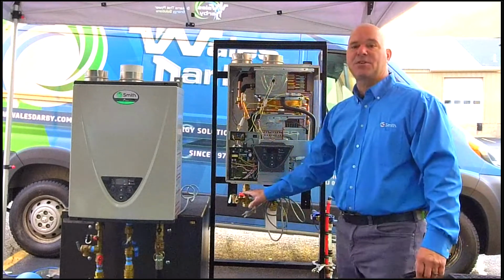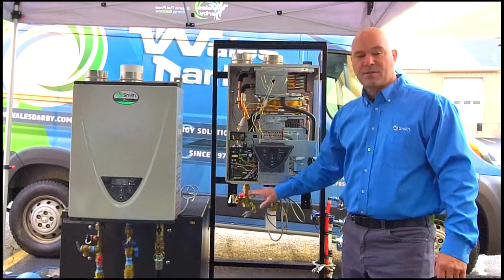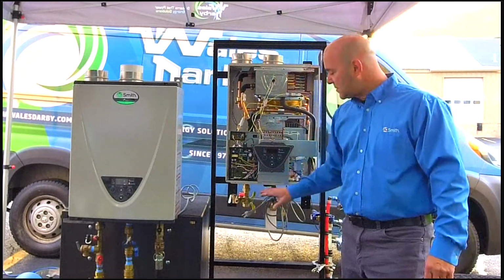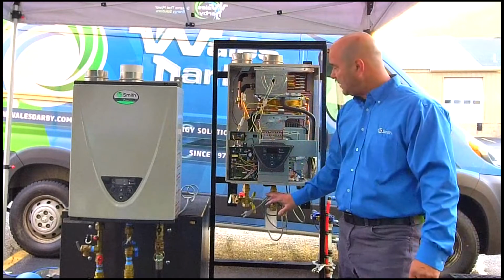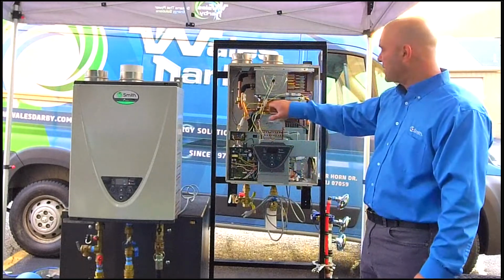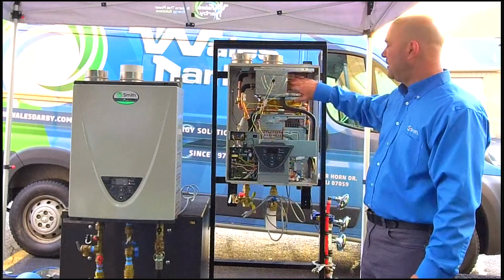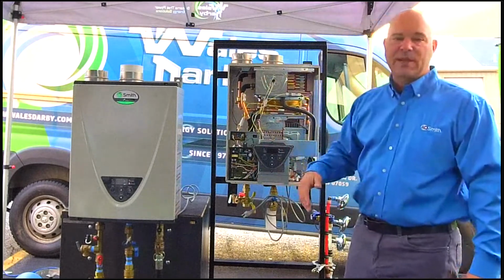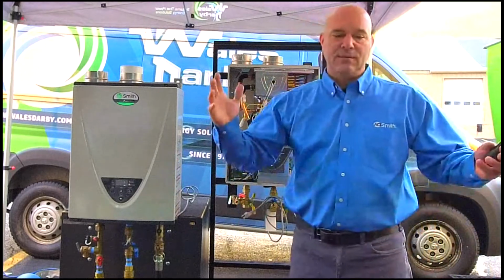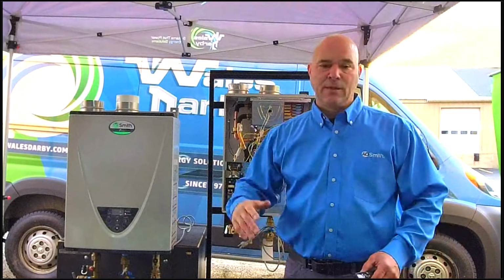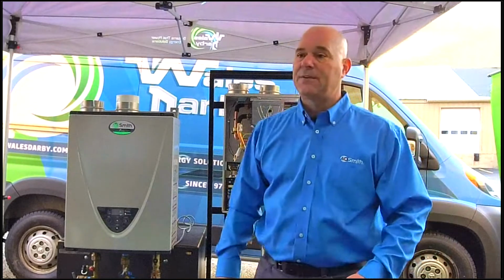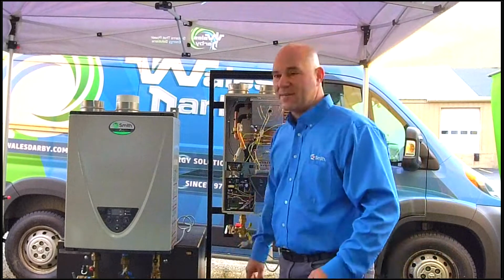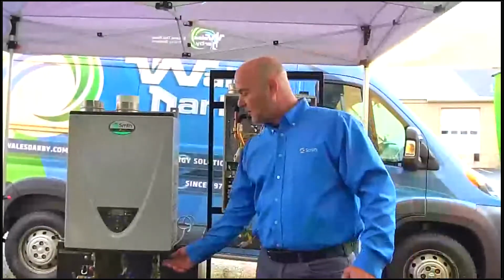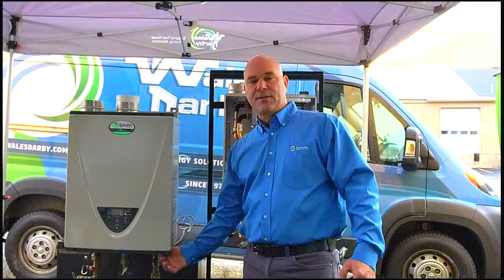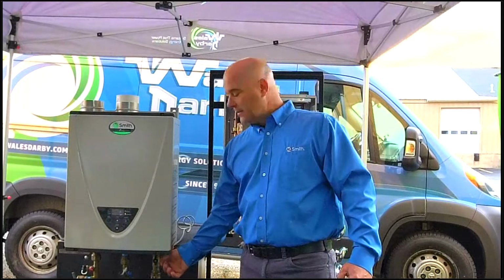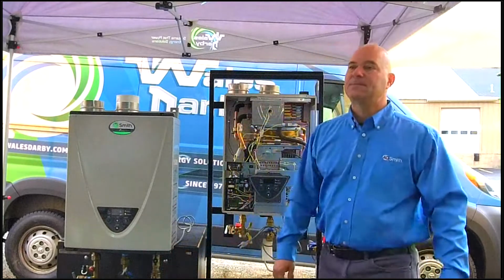The reason for that is we want to make sure that we have the ability to service the unit. If the unit needs to be serviced, we have the ability to flush the heat exchanger. Primary heat exchanger is here, this copper heat exchanger. The secondary heat exchanger is here, the stainless steel heat exchanger. We want to make sure we have the ability to flush them. You would use a vinegar, a real light chemical, and make sure you flush it out after you do it. And we'll touch on the process at the end. Never a bad idea. We have a screw thread here to put a neutralizer. We do come out of here slightly acidic, so it's never a bad idea to have a neutralizer.